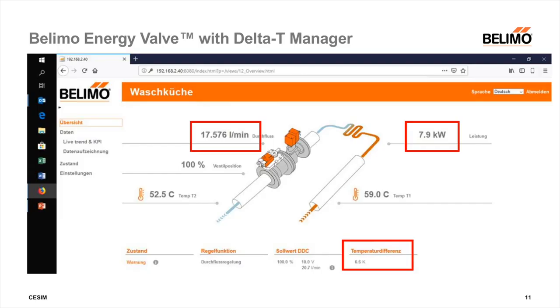The lower the return temperature, the better the efficiency, because there is more condensation heat in the gas. Therefore, the energy valve can ensure that this efficiency is guaranteed for condensing boilers. We can see from a practical example what such an increase in energy efficiency really means. The installation data show an output of 7.9 kilowatts, achieved with a flow rate of 17 liters per minute and a differential temperature of 6.6 Kelvin. These values can be massively improved with the delta-T manager.